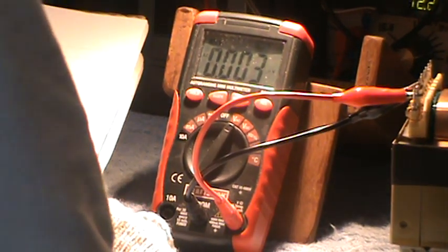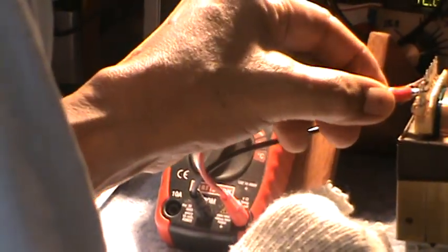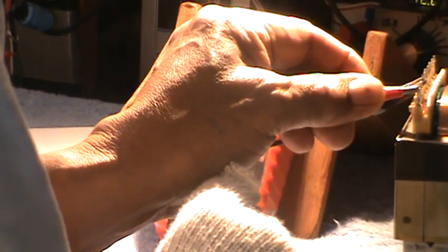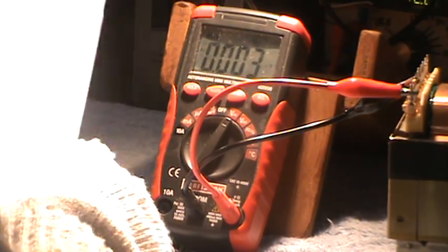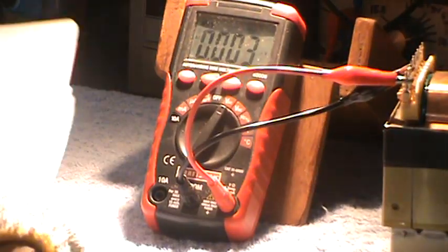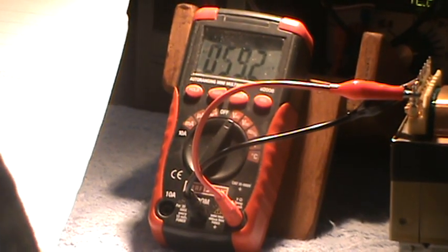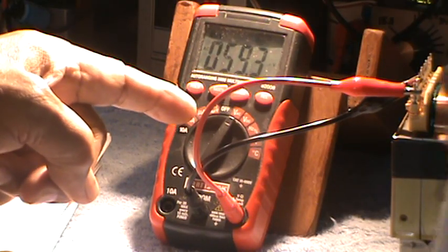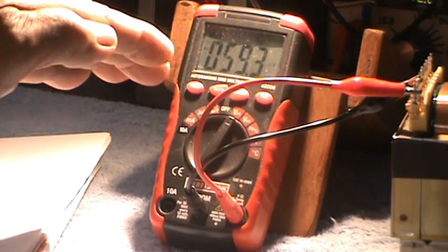The next one, terminals 8 and 10. Okay, that terminal 8. Then this one will be terminal 10. A while ago, across terminals 8 and 10, I measured the resistance of 0.7 ohms. So supposed to be, if we try to energize the primary, we could measure an AC voltage here. And what will be the AC voltage that will come out? The voltage across terminals 8 and 10 is 59.3 volts. Could you see it, guys? 59.3. Okay. That's an AC.